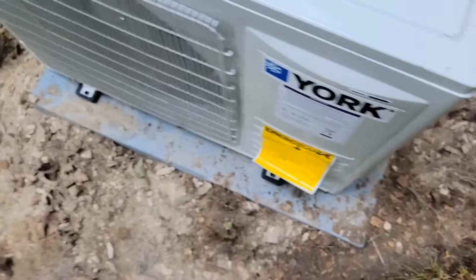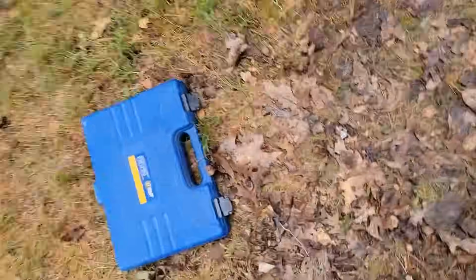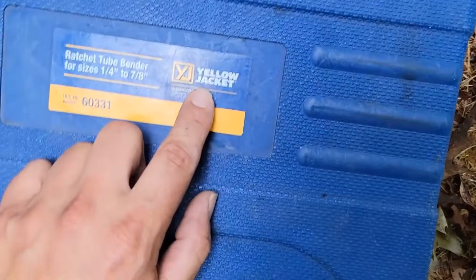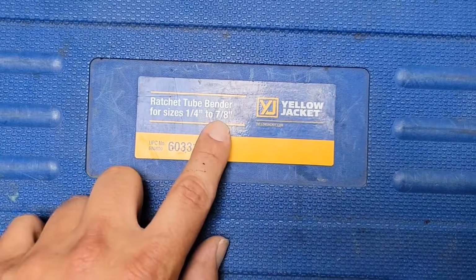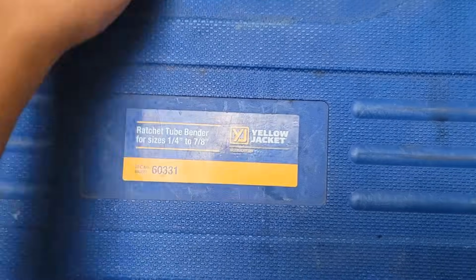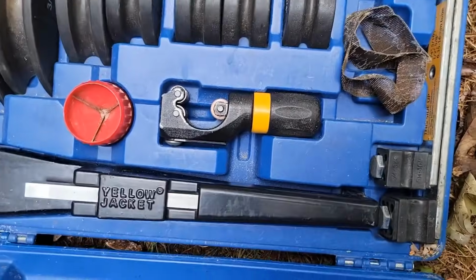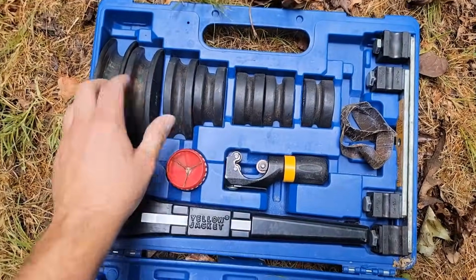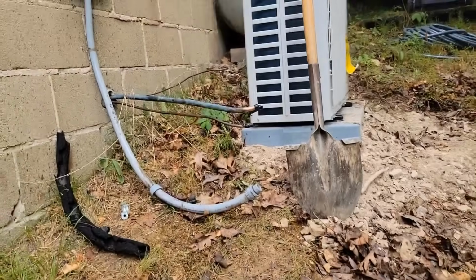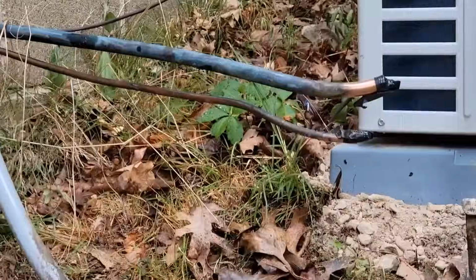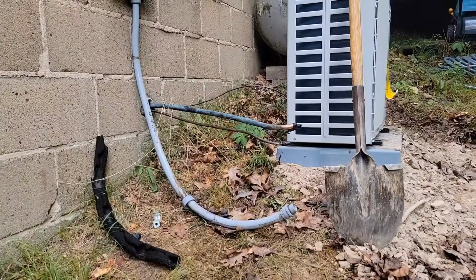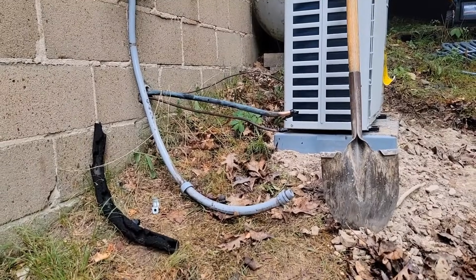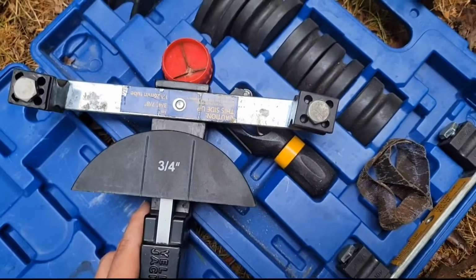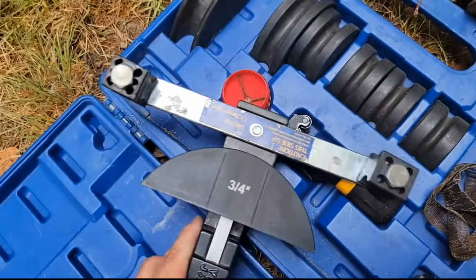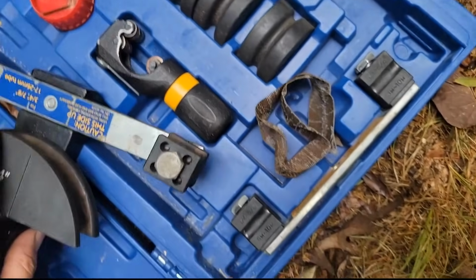We're going to need a tubing bender. And that's why we're using the Yellow Jacket ratchet tube bender. For sizes 1/4 inch to 7/8. Beautiful. That's beautiful. So we've got 3/4 and 3/8 tubing. 3/4 is a vapor line, 3/8 is the liquid line. It's really nice tube bender here. Got it set up for the 3/4. It's pretty easy to set up.